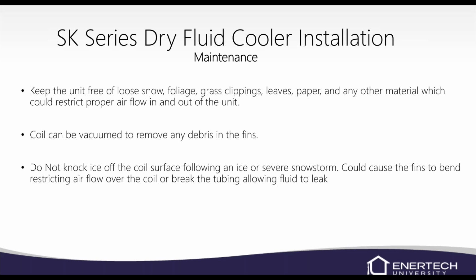You can vacuum the coil to remove any debris in the fins. I don't recommend knocking the ice off the coil surface following an ice or severe storm. It could cause the fins to bend or even break, and then you're going to have some water leakage. So if you want to get that ice off, you could run some water over. It's not really going to hurt the unit to run water over the air coil. I mean, it sits outside, so it's rated for outdoor operations. So getting a little bit of water on there is not really a big deal. But yeah, you can vacuum it as well.